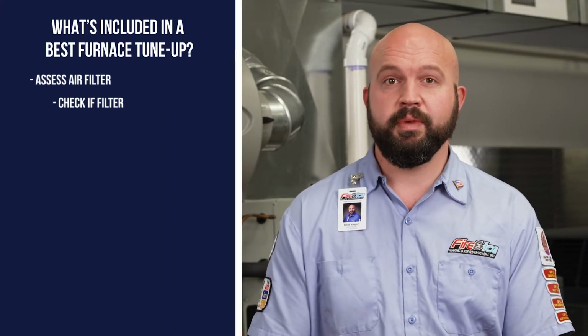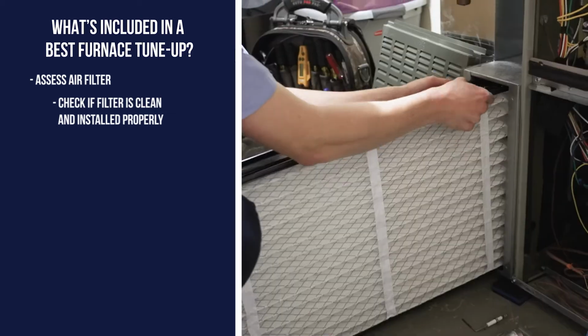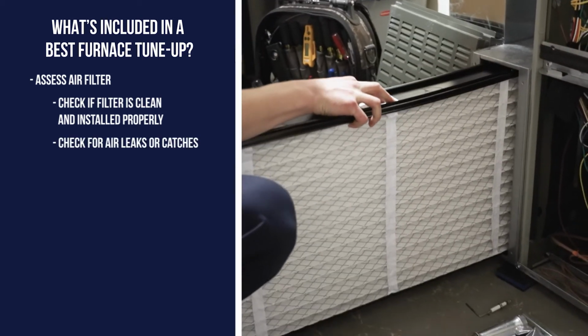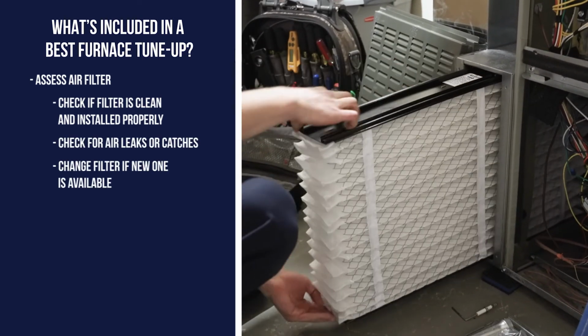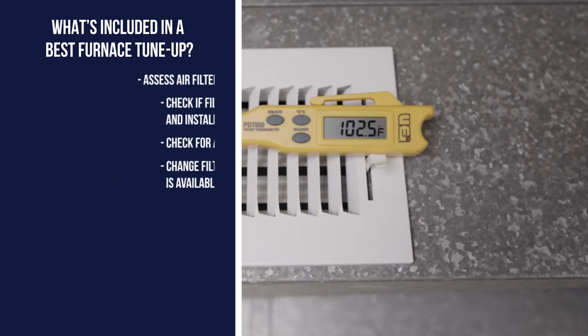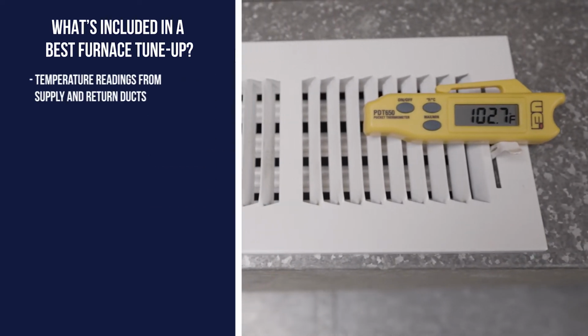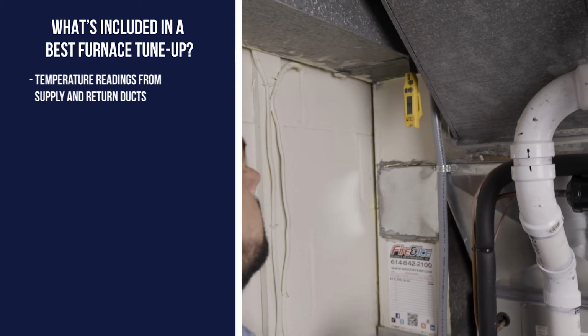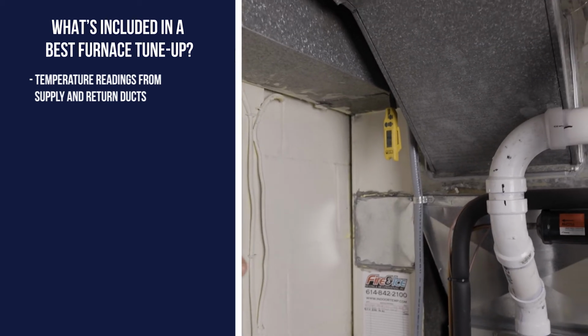Next, we check the filter to make sure it's clean and installed properly. We also check for any air leaks or catches around the filter rack. If a new filter is available, we'll take time to replace it. Next, we take a series of temperature readings from both the supply and return air ducts to see if they are within normal ranges for your furnace.